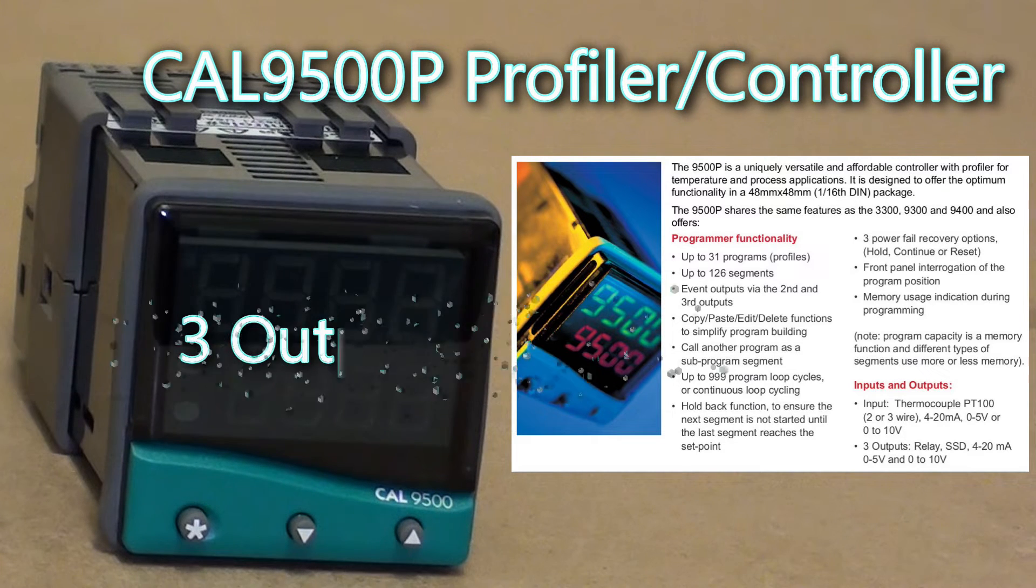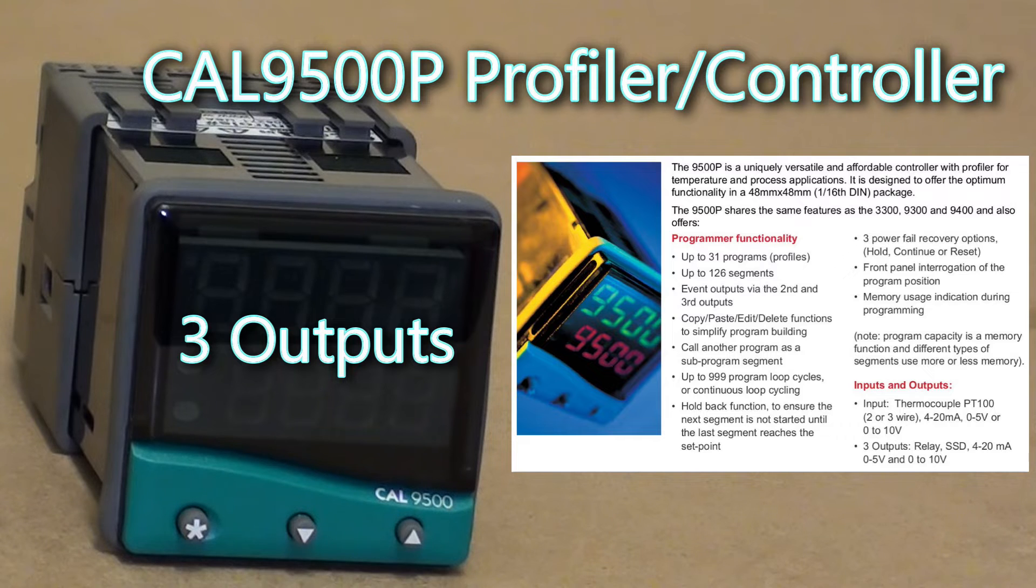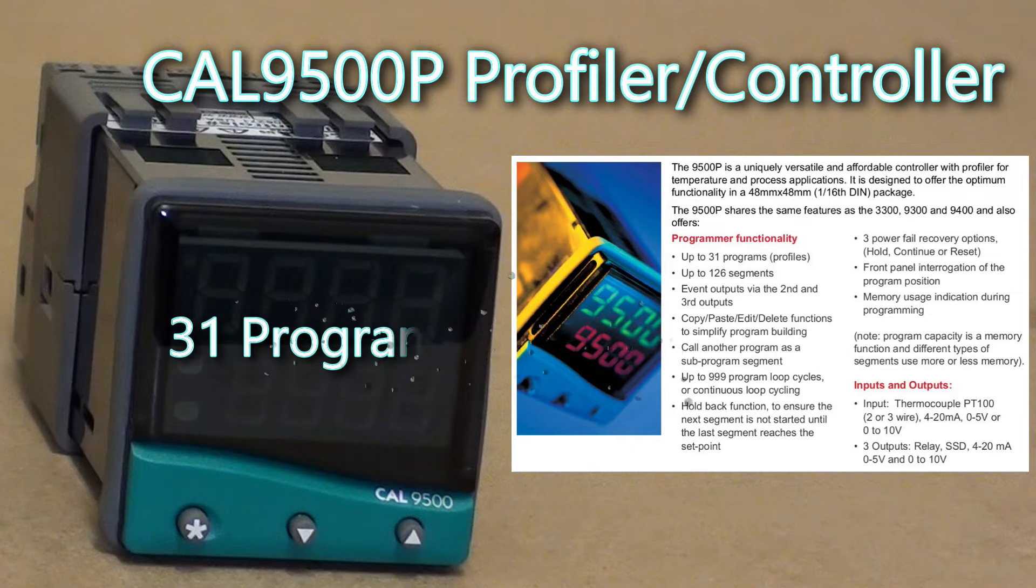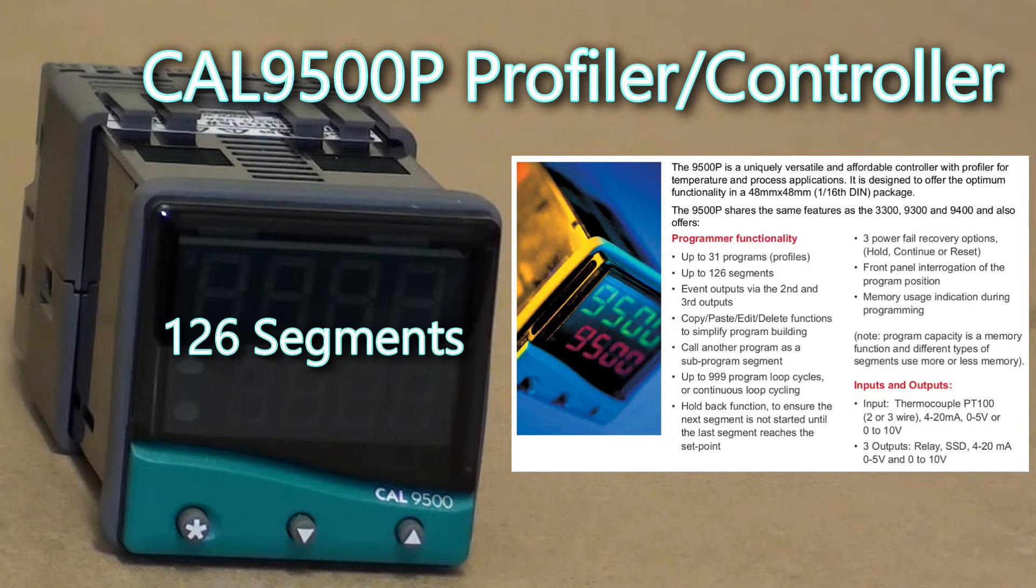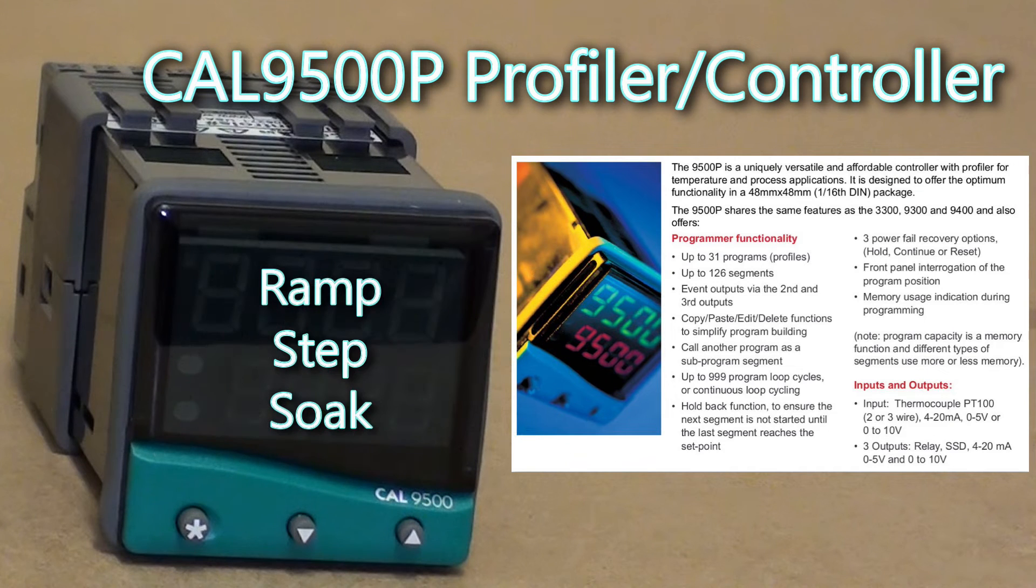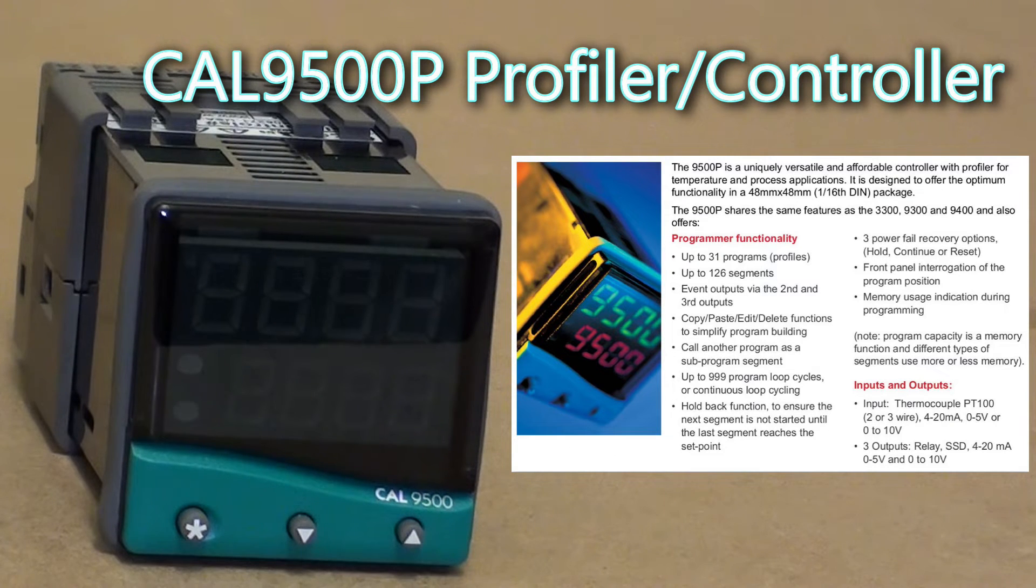There are a total of three outputs, either solid state drive SSD, relay, or analog. The programmer function offers up to 31 programs or profiles with up to 126 segments. Program functions can be ramp, step, or soak. The power supply required is 100 to 240 volts AC.